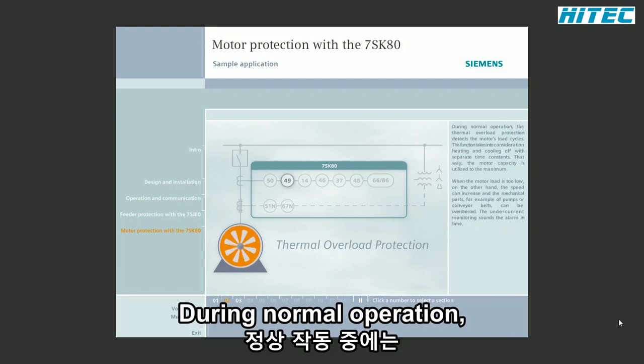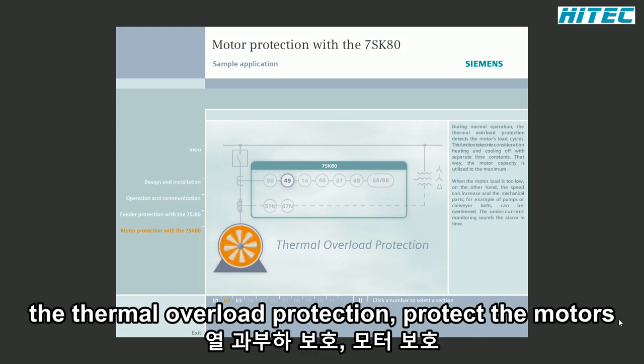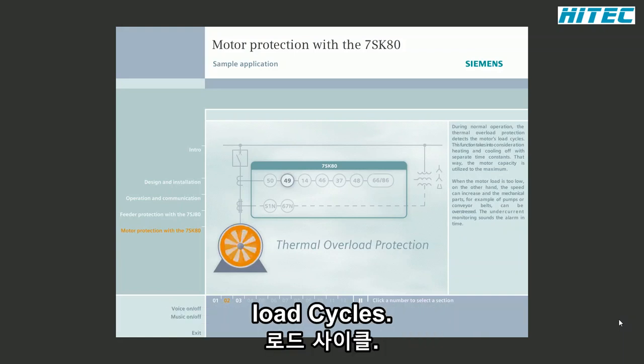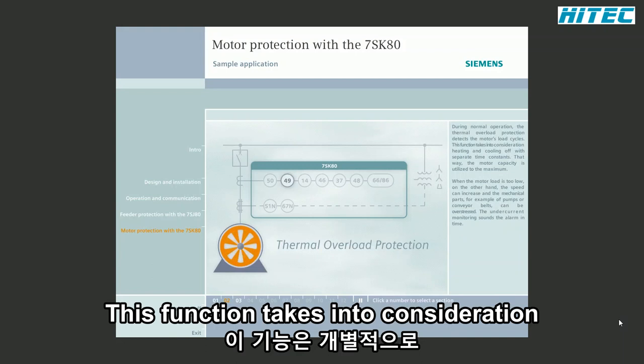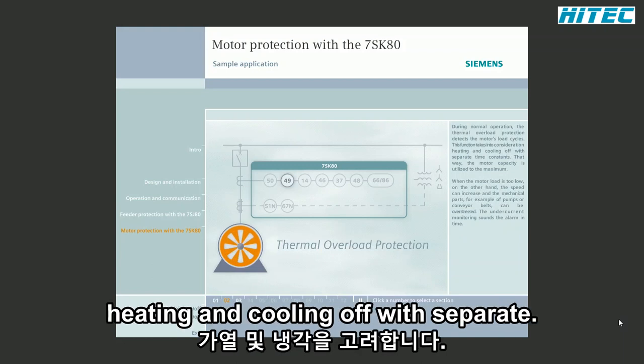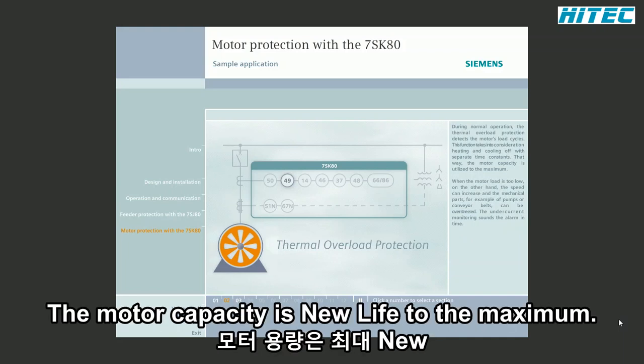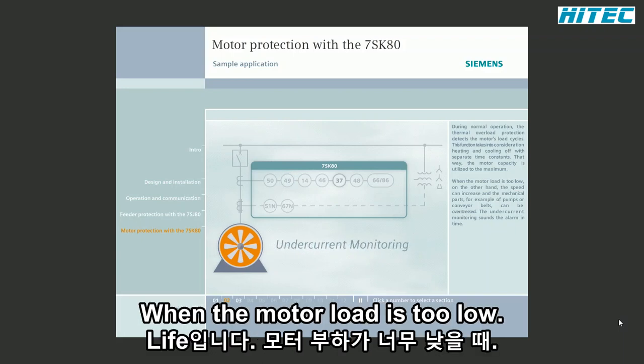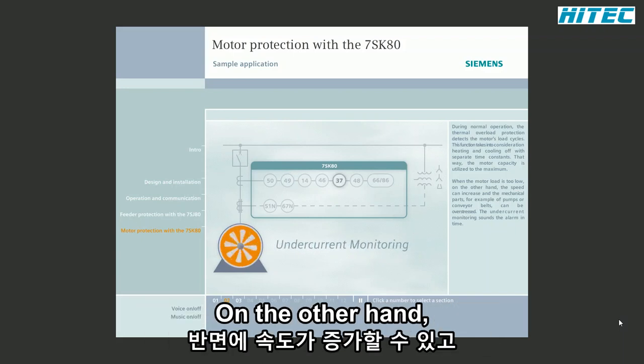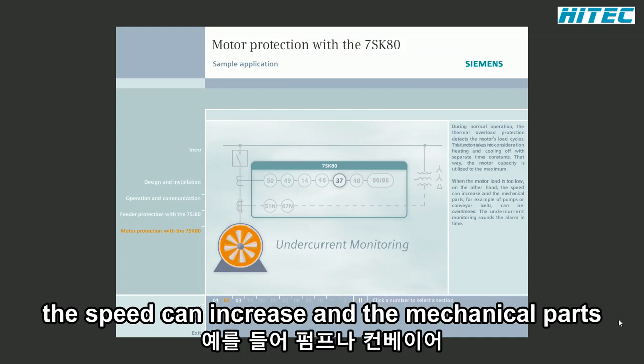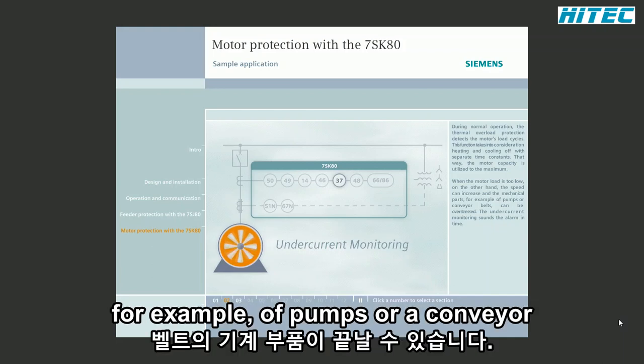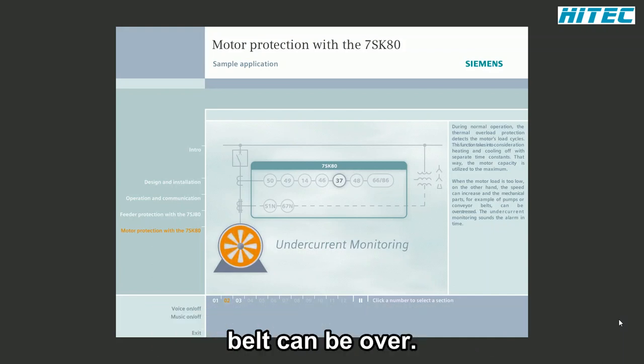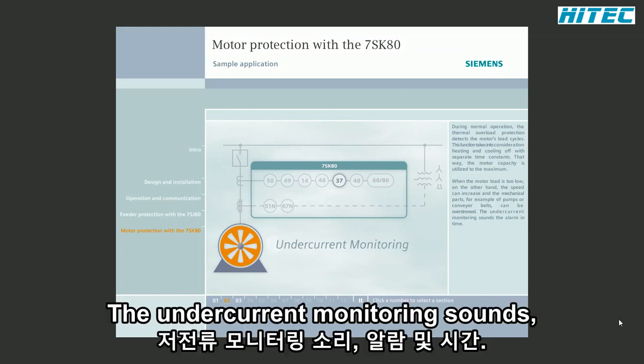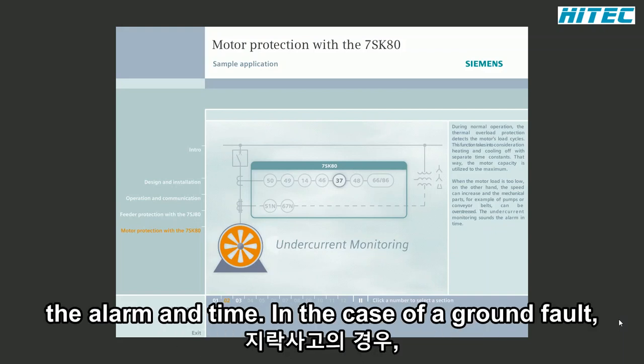During normal operation, the thermal overload protection detects the motor's load cycles. This function takes into consideration heating and cooling off with separate time constants. That way, the motor capacity is utilized to the maximum. When the motor load is too low, on the other hand, the speed can increase and the mechanical parts, for example of pumps or conveyor belts, can be overstressed. The undercurrent monitoring sounds the alarm in time.